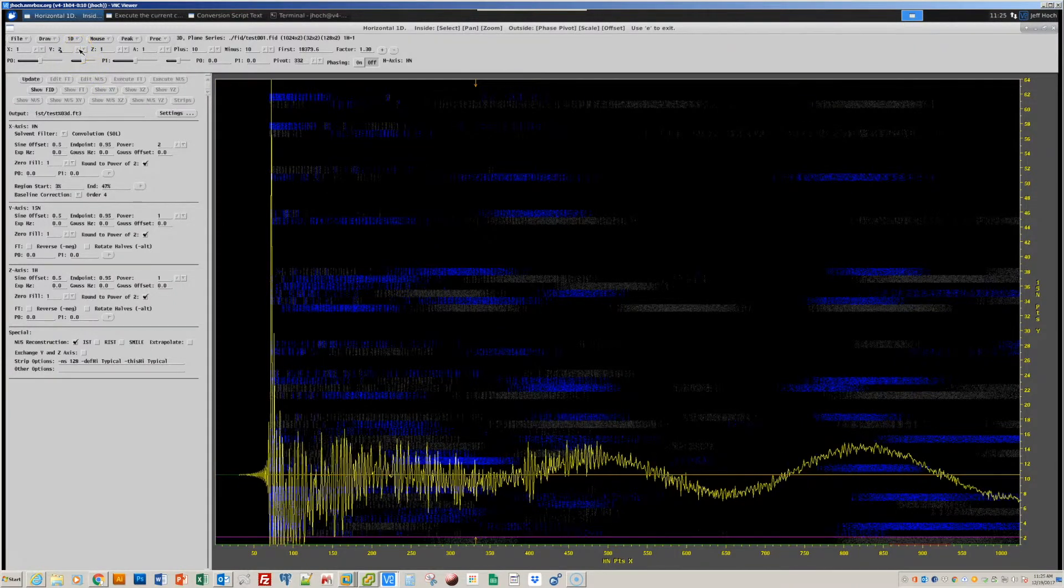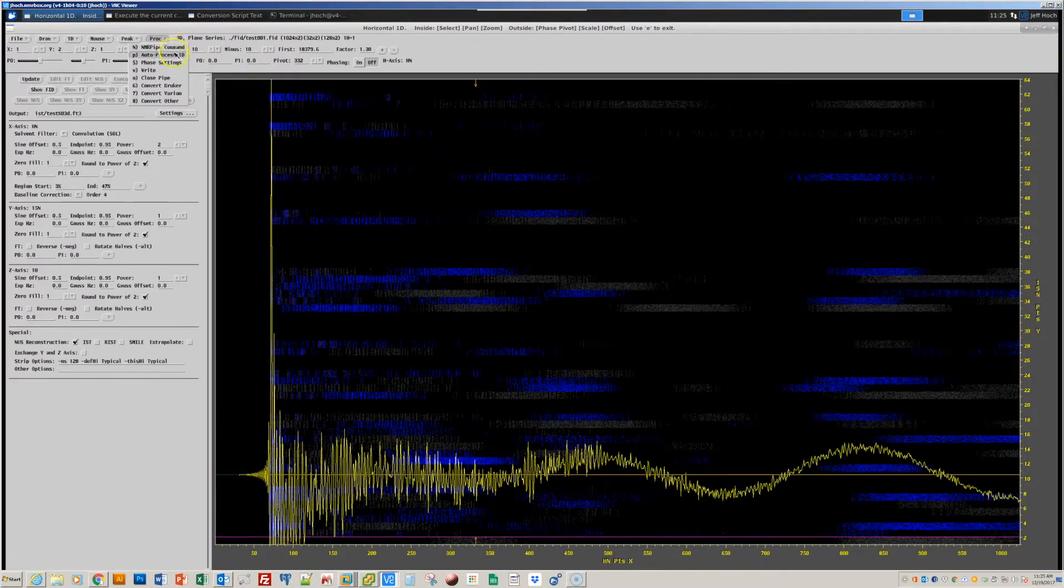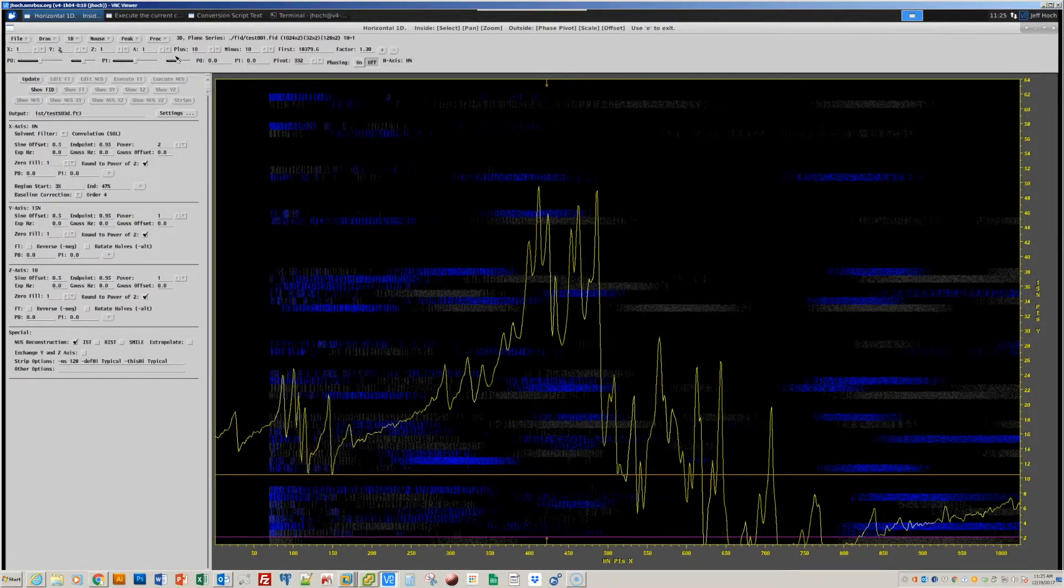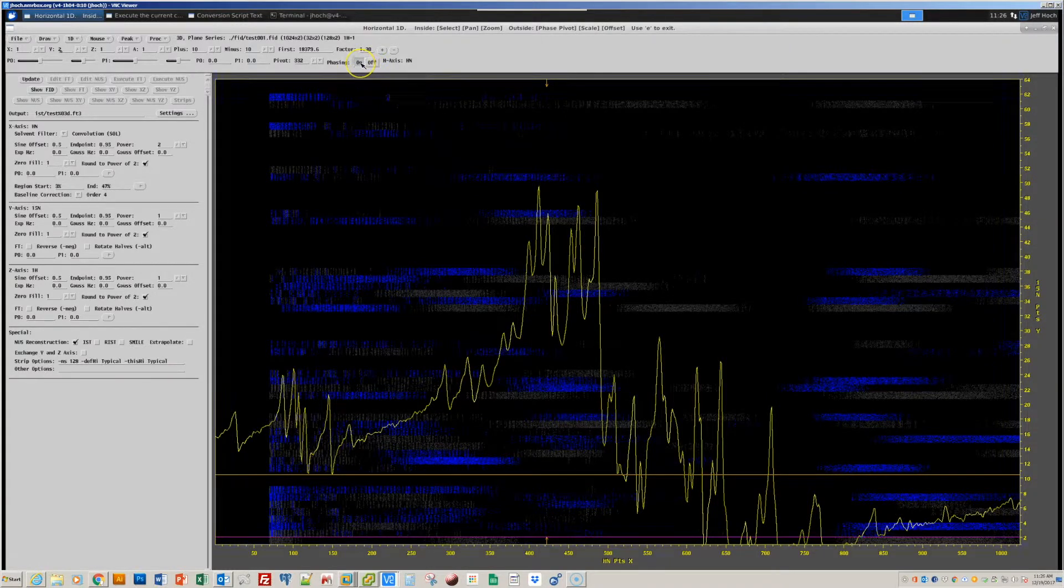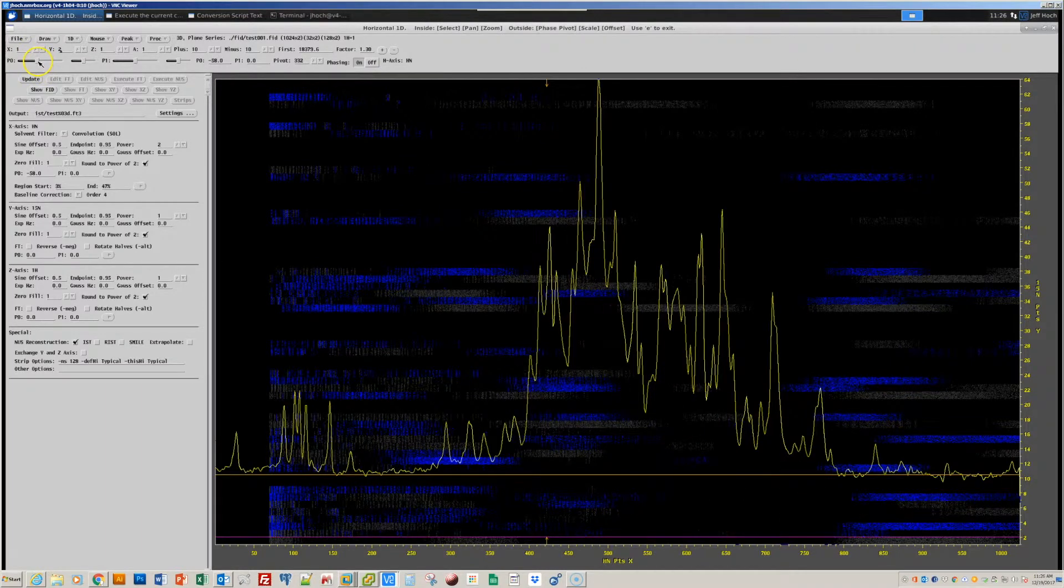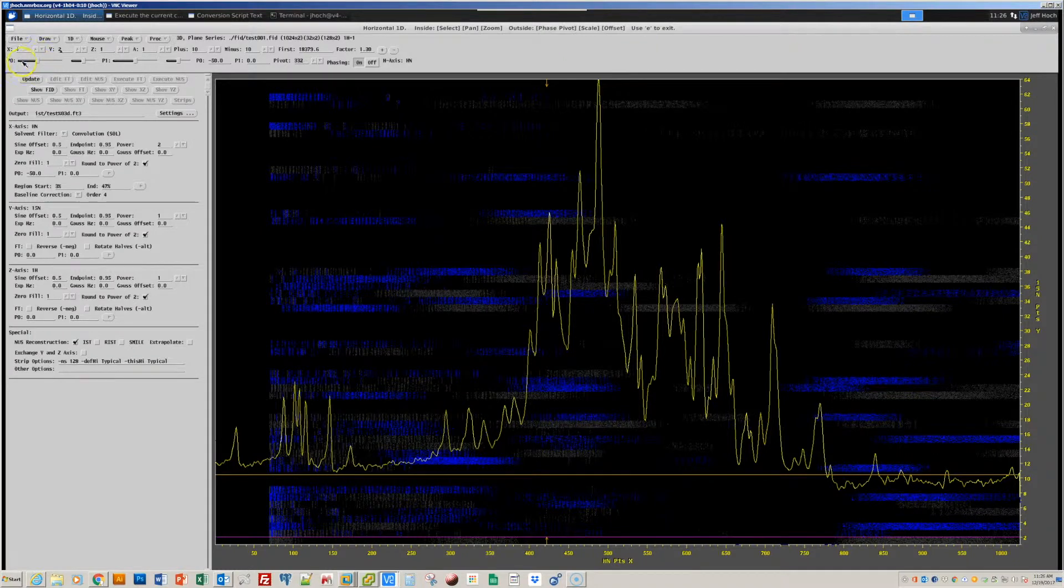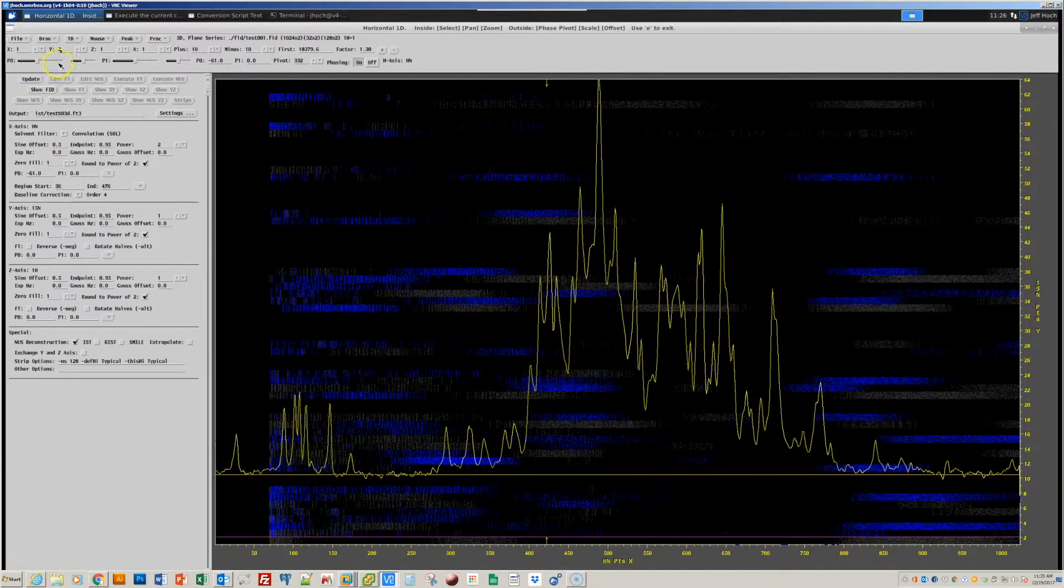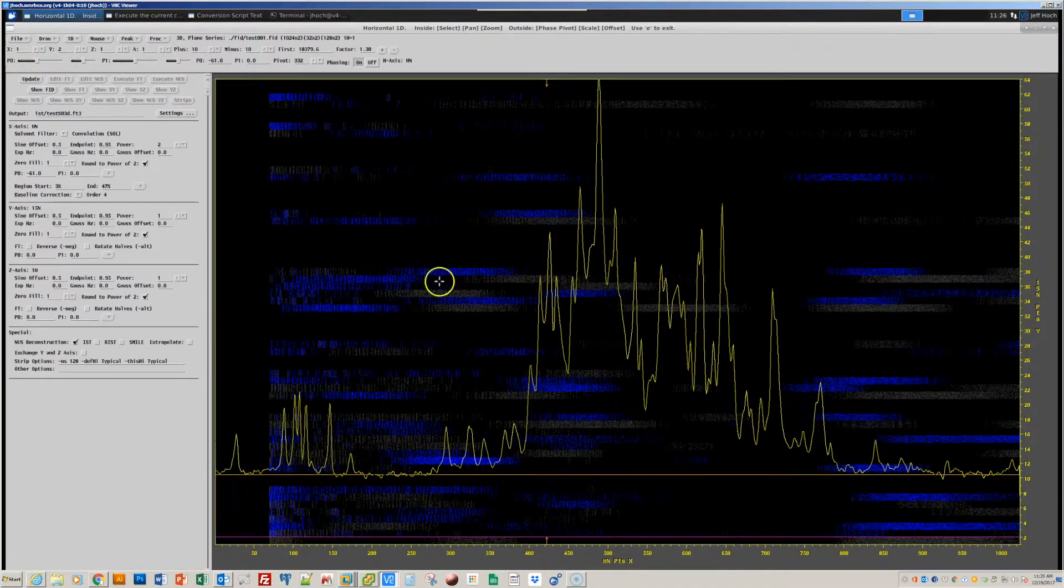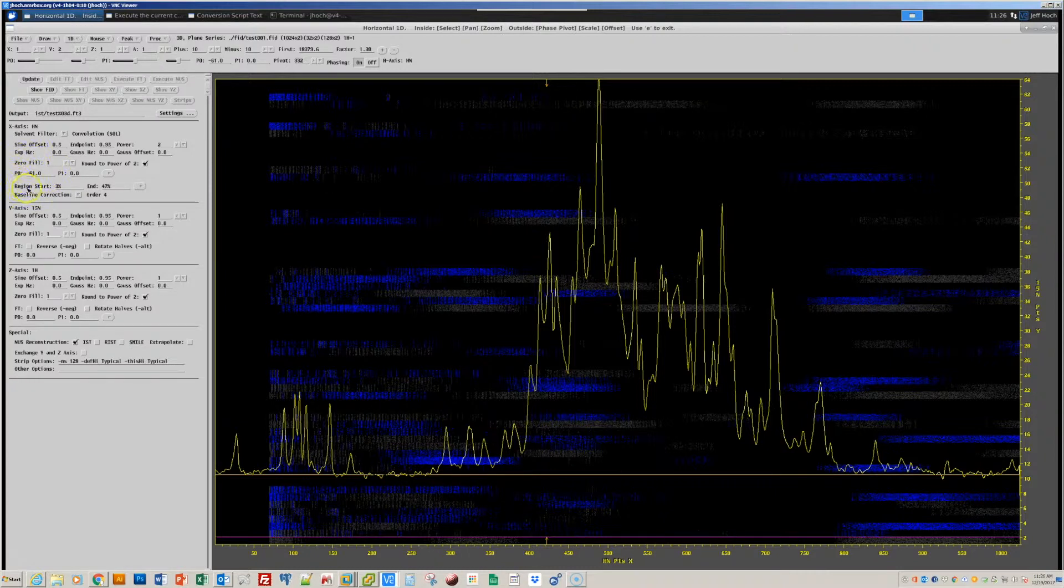Under the processing menu, I'll use the command called auto-process 1D, and that will create a spectrum from this 1D data set that we can use to make an initial phase correction for the directly detected dimension. So in the command panel, we can turn on interactive phasing with this button, and then the sliders are active to adjust phase. I can drag the slider to adjust the phase continuously, or click on the slider to increment or decrement the phase value. So here's the phase correction value that I've established. And if you look in the processing window, you can see that that parameter has been inserted in the command line entry.